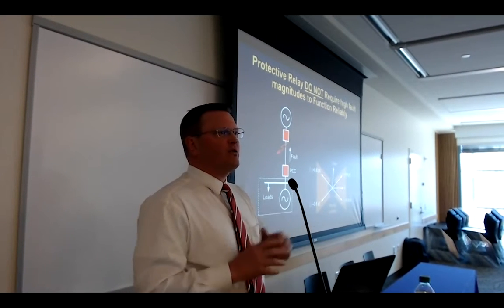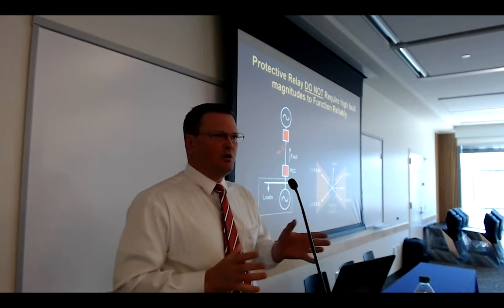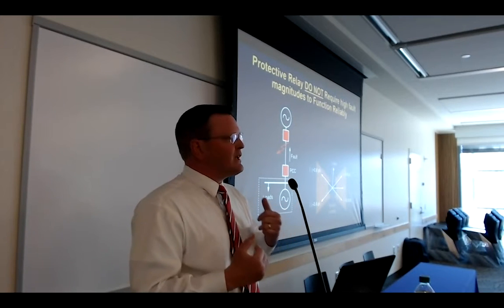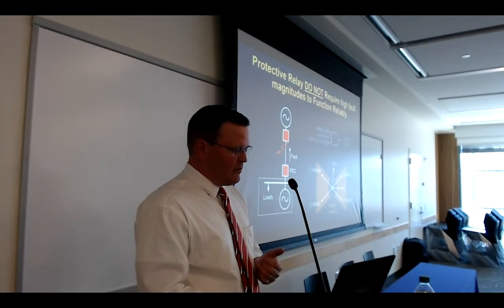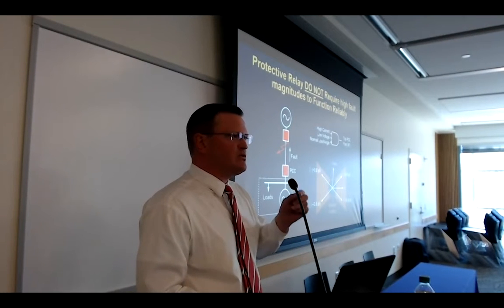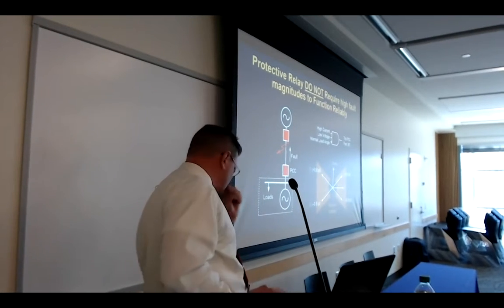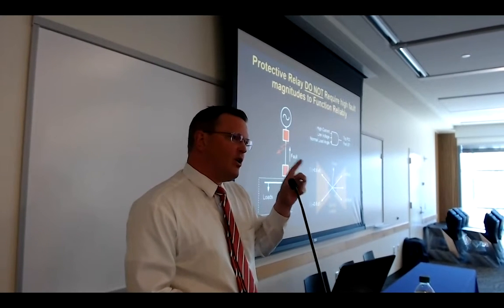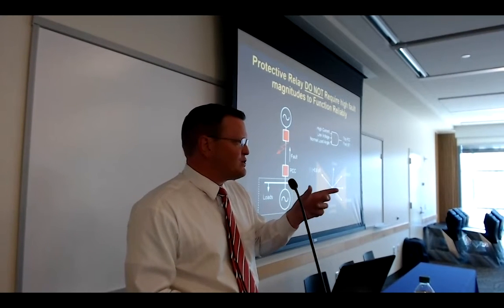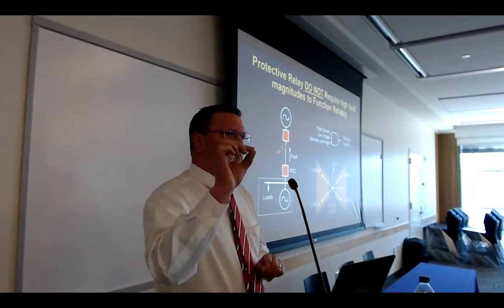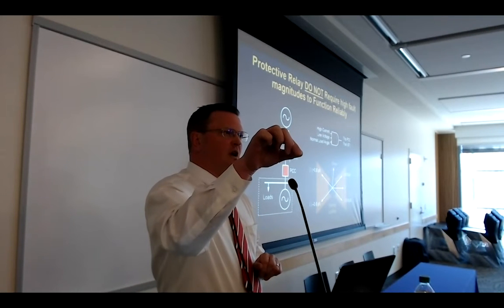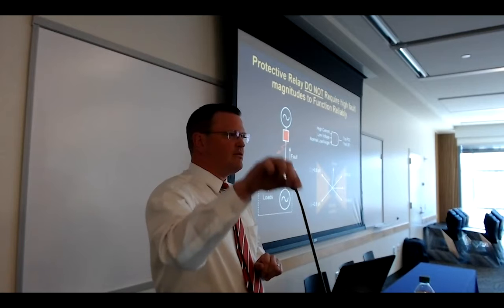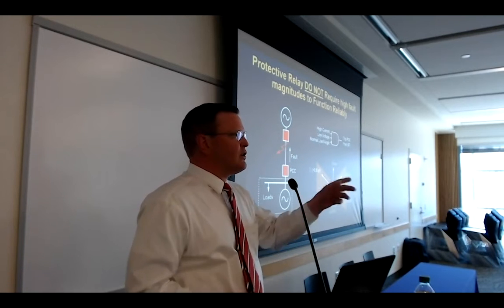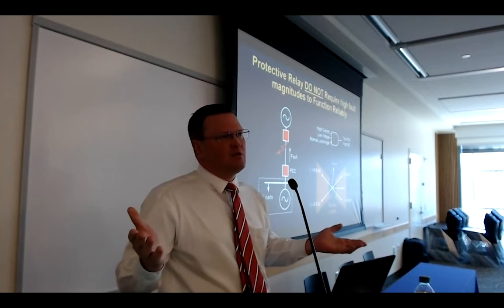Now, I've shown you a positive sequence current and voltage. Put this in a negative sequence and we get some advantages. The way this works is we just need some level of positive, or in this case negative, sequence voltage and current to calculate the impedance on a continuous basis every few milliseconds. And when the impedance goes in the wrong place, I can make a decision to trip.